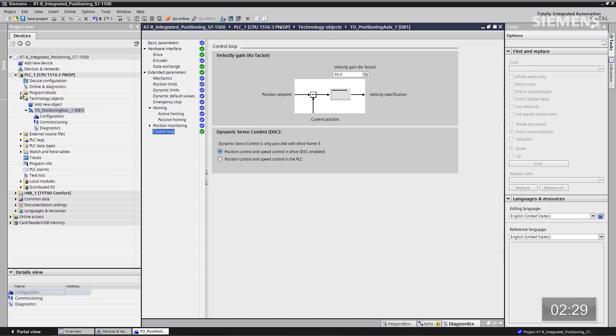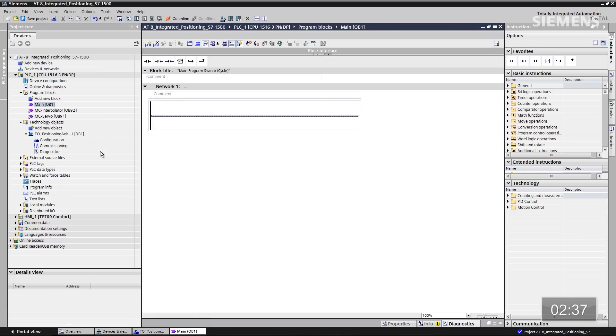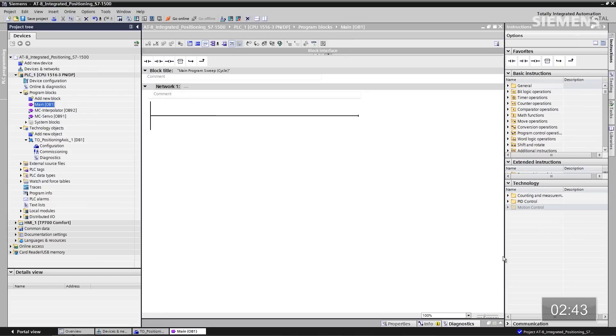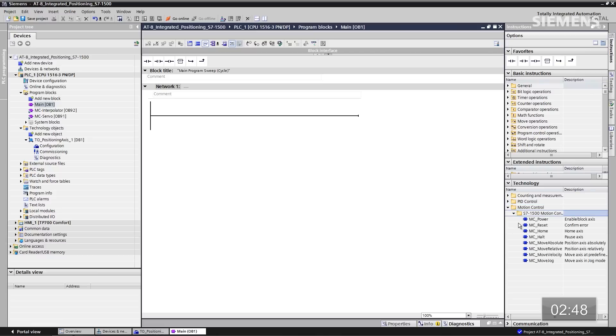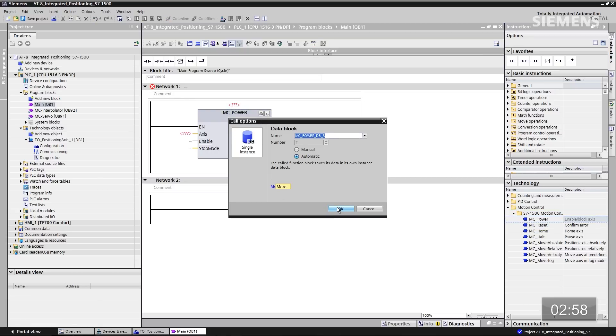Let's now go over to our program blocks. As you can see, I have two new blocks here — two MC blocks for the interpolator and the servo. Give focus to the main OB and double-click on it. In our main OB we have no program. I want to come over to the task card and go down to the technology section for motion control. Now you can see our PLCopen blocks that are available to us for programming. The first one I'd like to use is the MC_Power — let me drag and drop this into the project and accept the default data block.